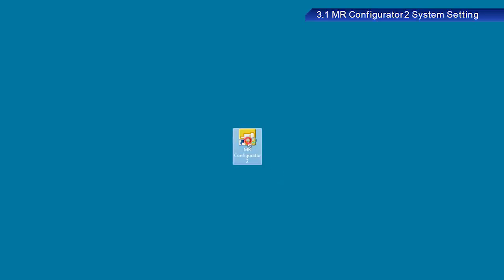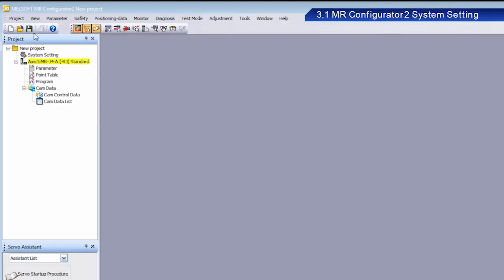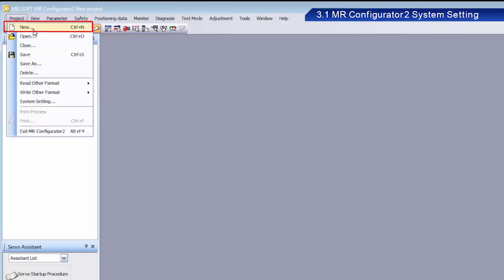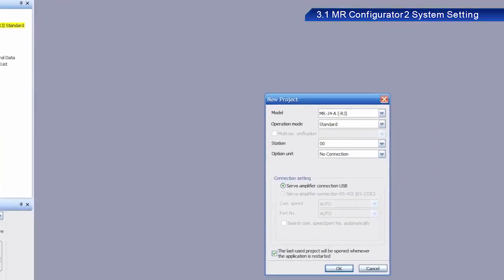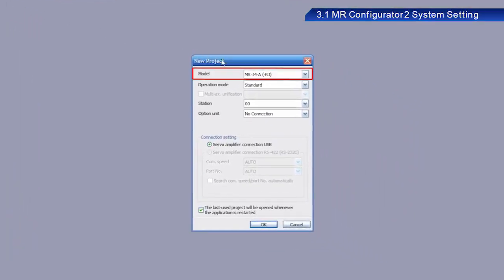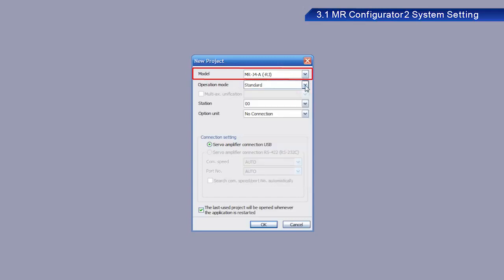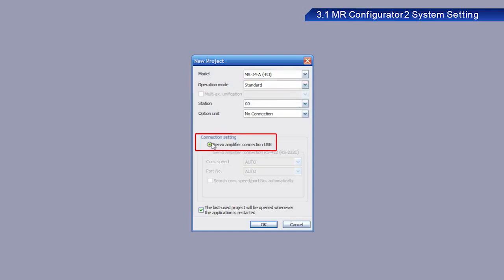First, start MR Configurator 2 on your PC. The version of the software used in this training is 1.60N. From Project, click New Project. Select MR J4A RJ in the Model menu. Select Standard in the Operation Mode menu. Select Servo Amplifier Connection USB under Connection Setting. Click OK.